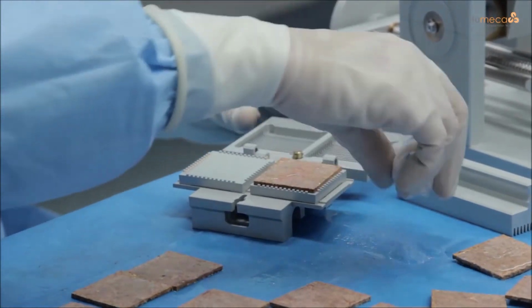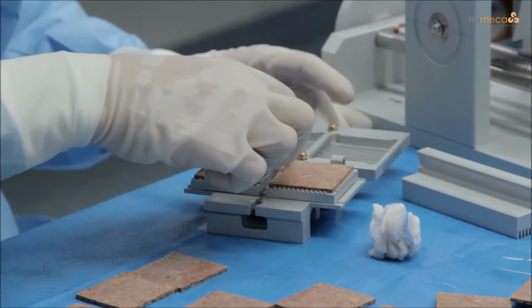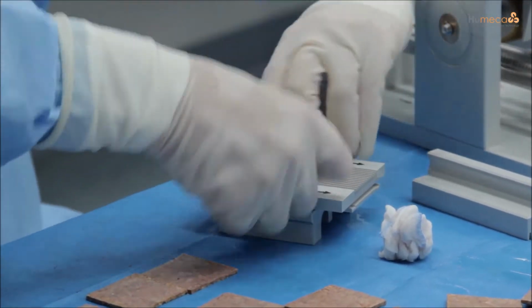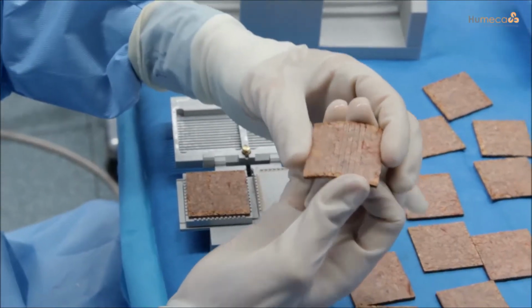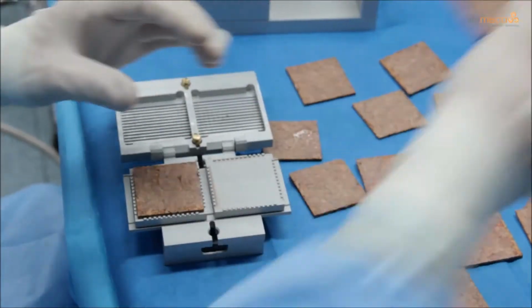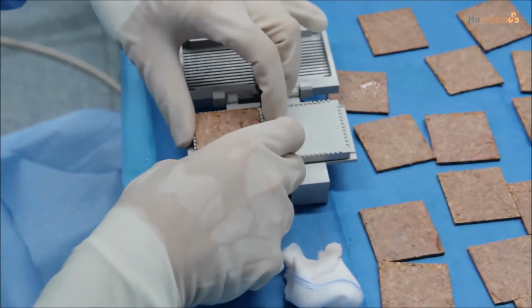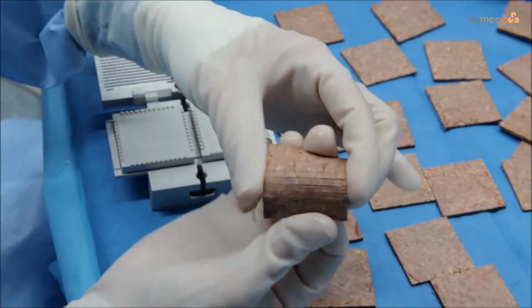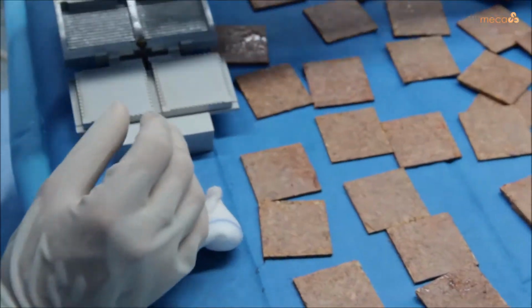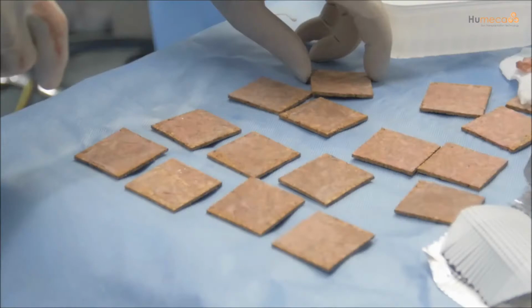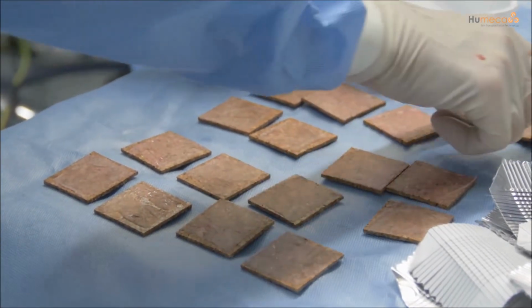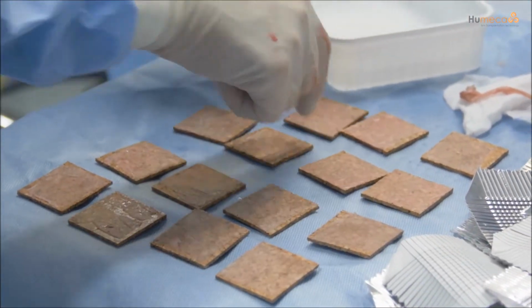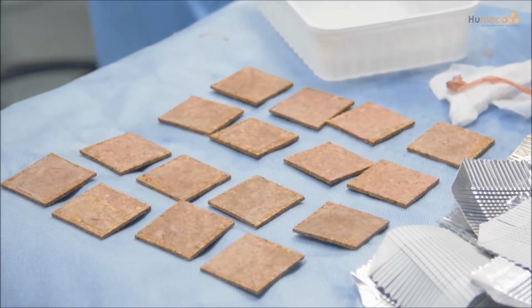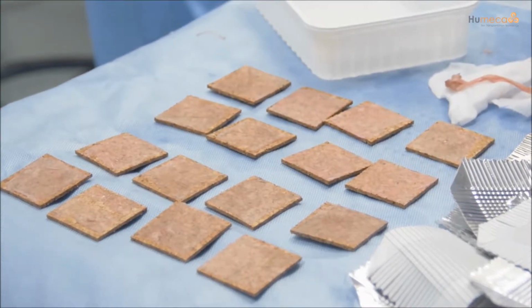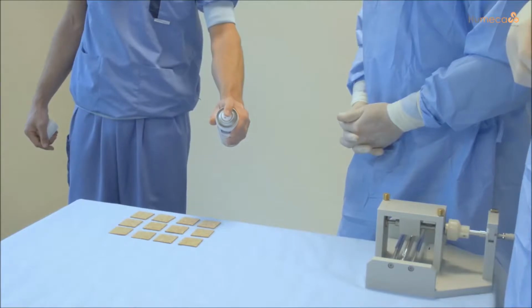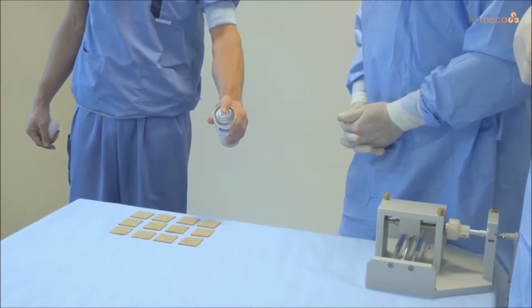Always place a second cork plate in the other cork holder to facilitate optimal cutting of the graft. Check if the cut has been done twice by bending the cork plate gently. By cutting the cork plate twice, 196 individual skin islands have been created. Place the cork plates with the skin on a flat sterile surface that is covered with a sterile drape. Put the cork plates a certain distance from each other. Set the cork plates away from other items to prevent them getting sprayed as well.